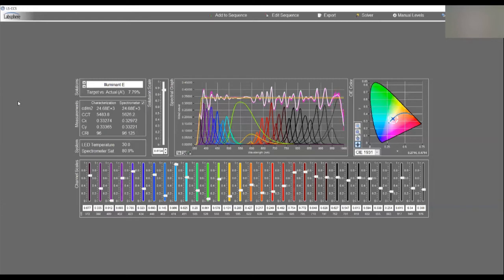With our FT2300, we have a tungsten halogen light source in there, which is a very stable source. We calibrate this FT2300 and characterize it for spectral radiance using that halogen source inside the sphere and the spectroradiometer inside the sphere, and a NIST traceable spectral radiance calibration through the port. That spectral radiance calibration is transferred to that tungsten source inside the sphere, and that can be used to recalibrate this spectral monitor, which is the pink line.